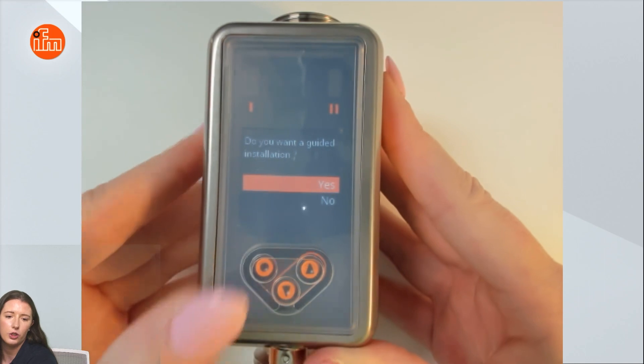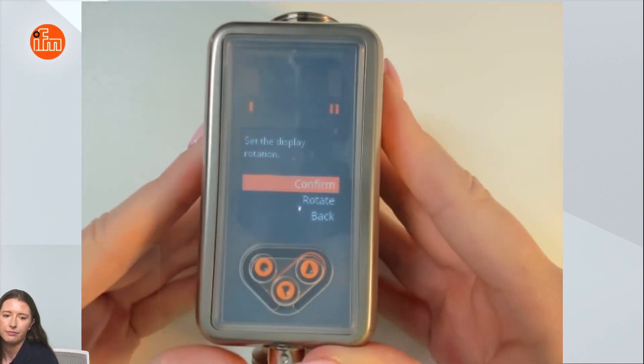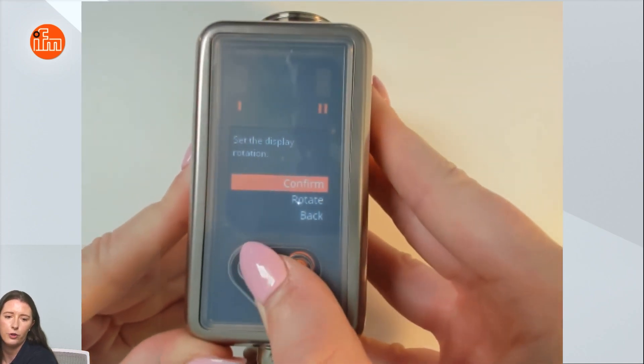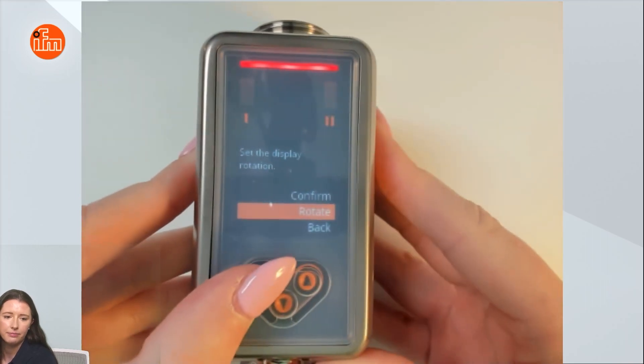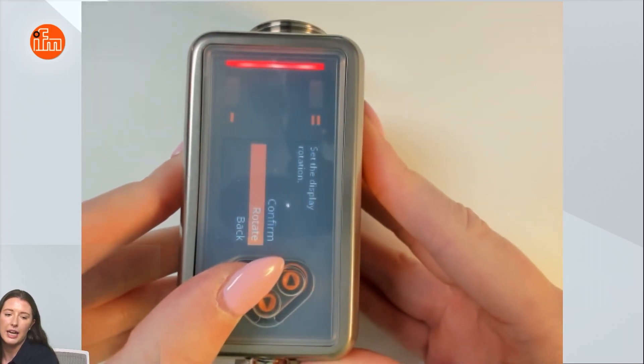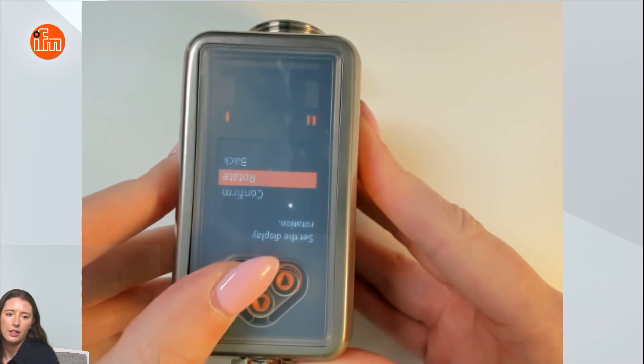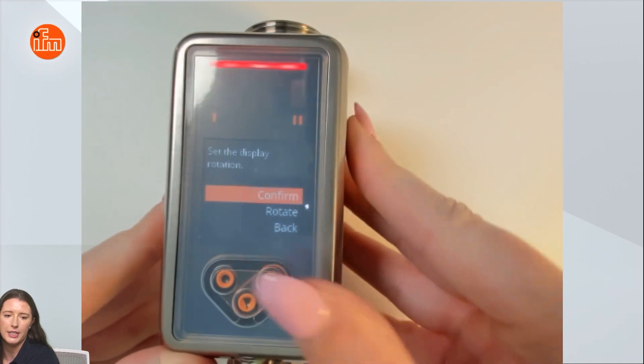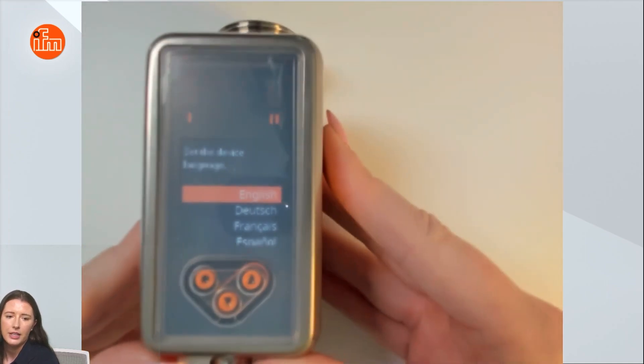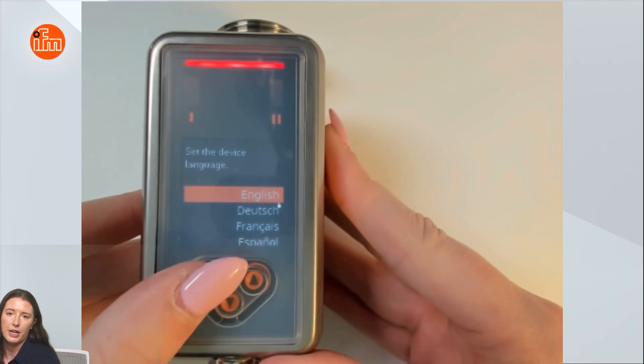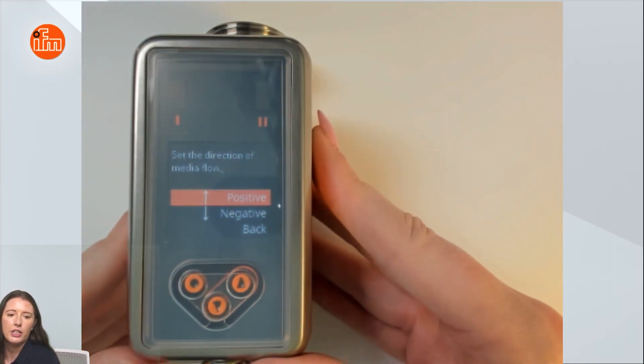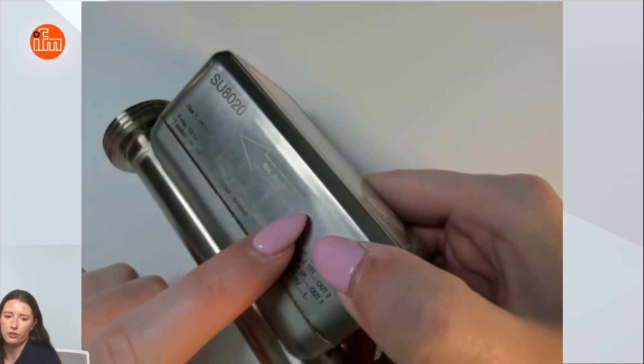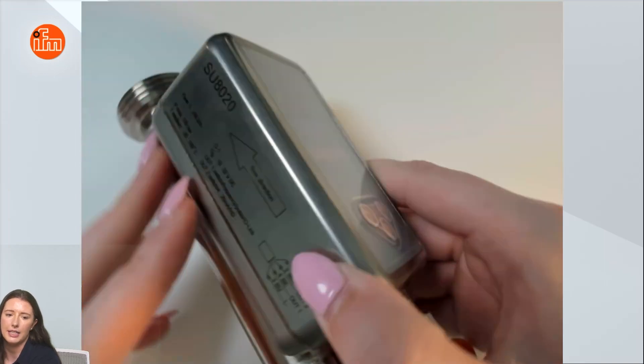If you want to go into this installation wizard you'll press yes, and then it's going to ask you to select the display rotation. You can confirm, or if you press down and enter it will rotate the display, and if you keep pressing rotate it will turn it 90 degrees each time. When you get it to where you want it to be you'll press up and press confirm. Next it's going to ask you what language you'd like. I'm going to press English, and now it's going to ask you to set the direction of the media flow. Positive would mean that flow is flowing in the direction of the arrow and negative would mean it's flowing against the arrow.